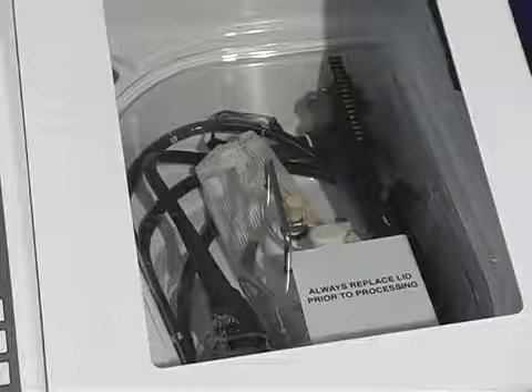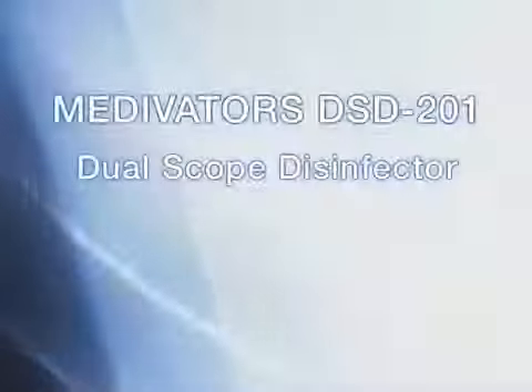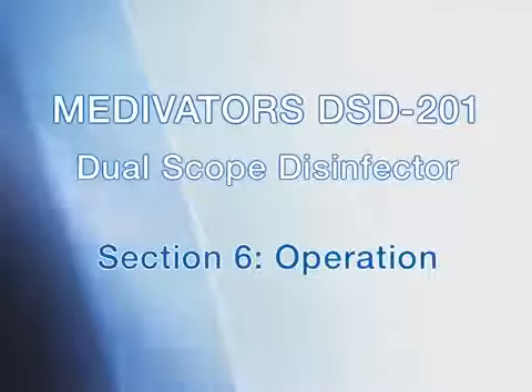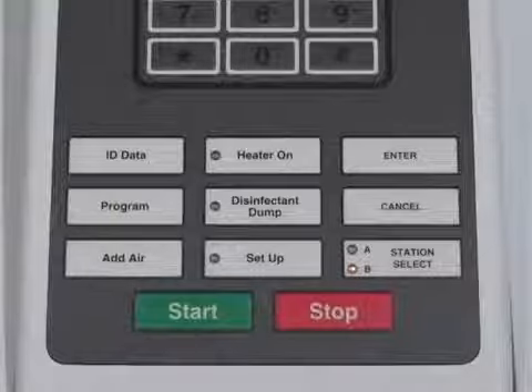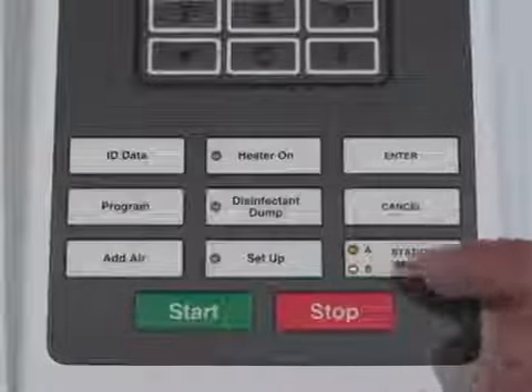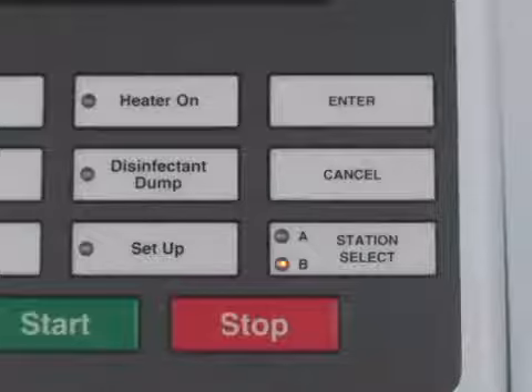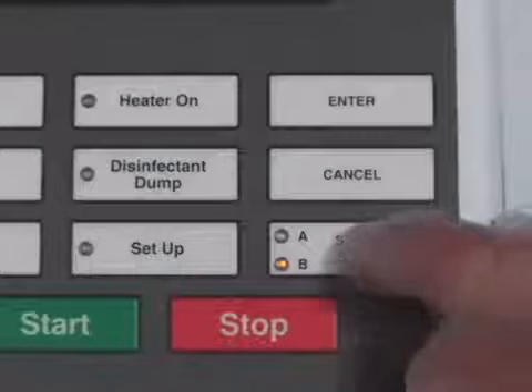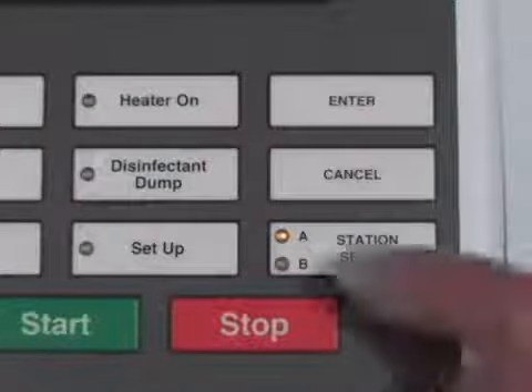Close the station lid. The distal end should be positioned so that fluids passing through it are clearly visible. The distal end of the scope should be tucked underneath and must not point upwards toward the floating lid. This is to prevent fluid from going up and on top of the floating lid. Press the Station Select function key on the control panel. If you are using the left basin, select Station A. If you are using the right basin, select Station B.